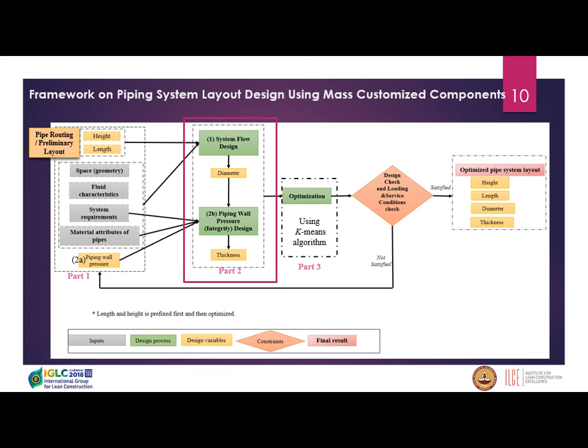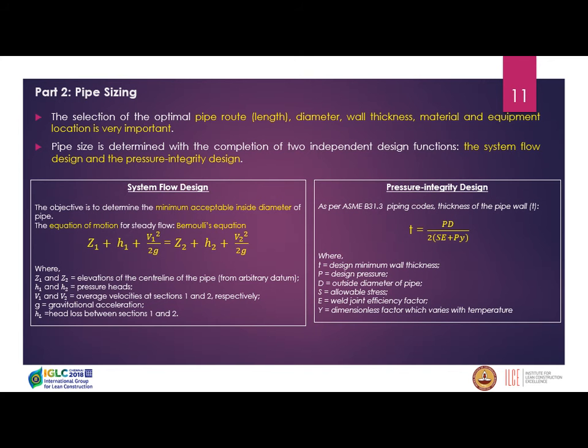Part two involves pipe sizing after obtaining the preliminary pipe layout. It involves two independent design functions: system flow design and pressure integrity design. The system flow design gives the minimum acceptable diameter using Bernoulli's equation and the equation of motion — a summation of datum head, pressure head, and velocity head. The pressure integrity design, given by code, provides the pipe thickness using design pressure and stresses.